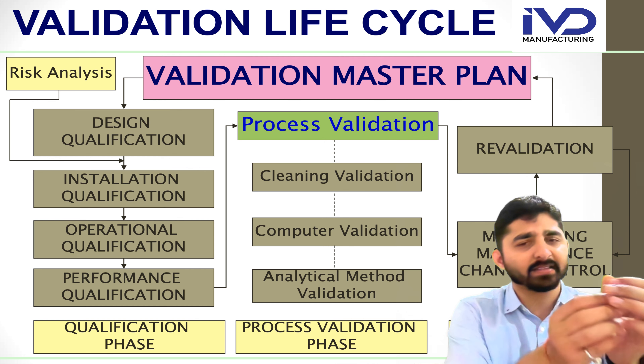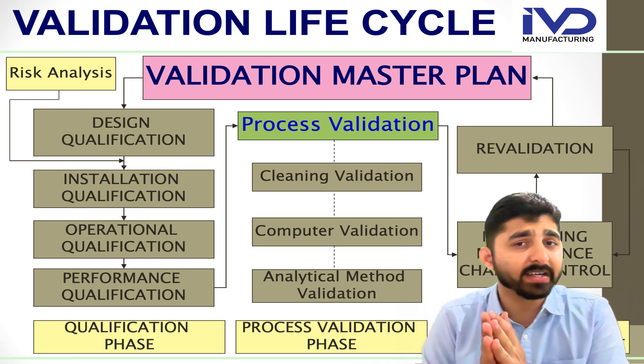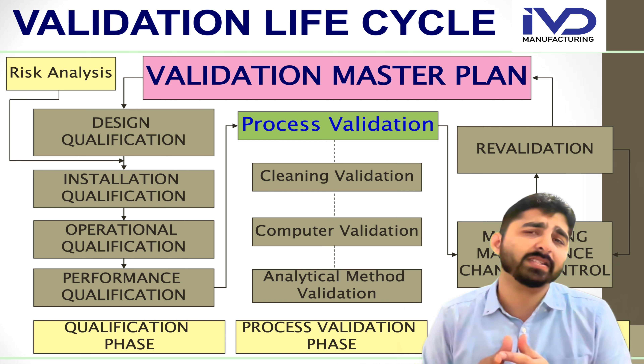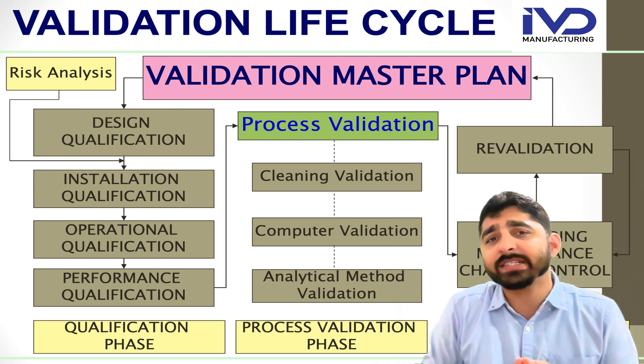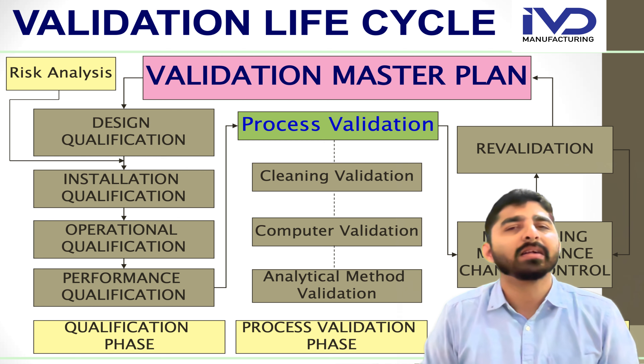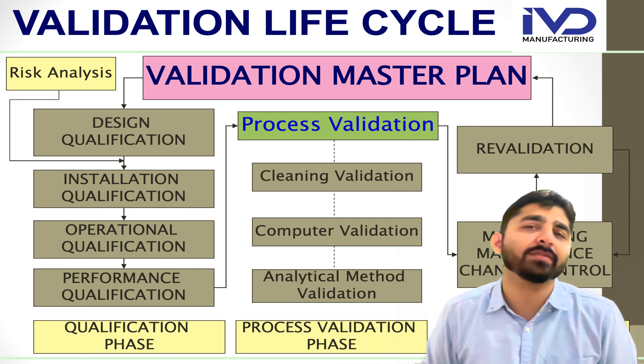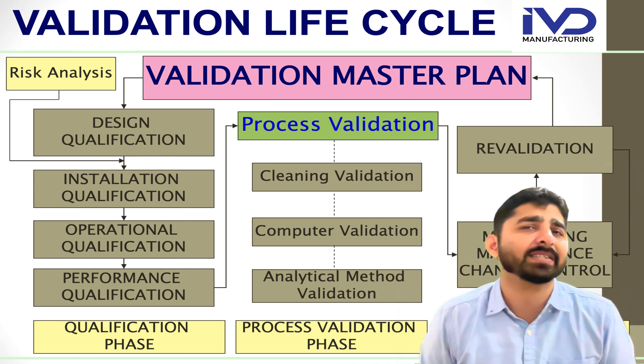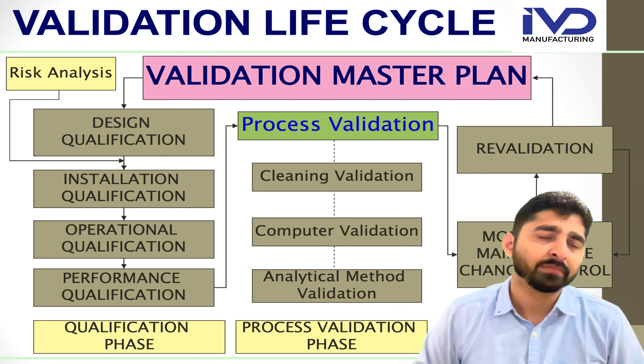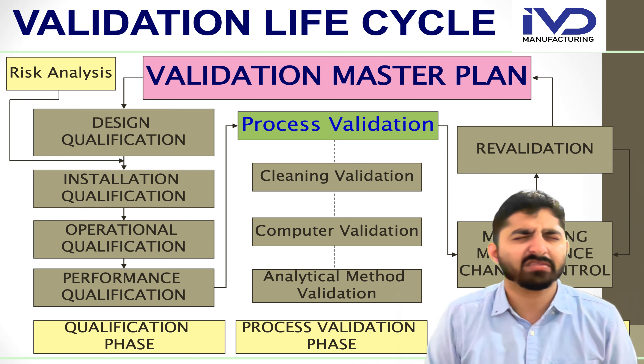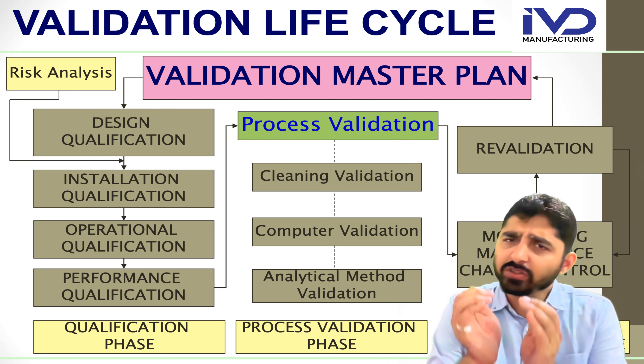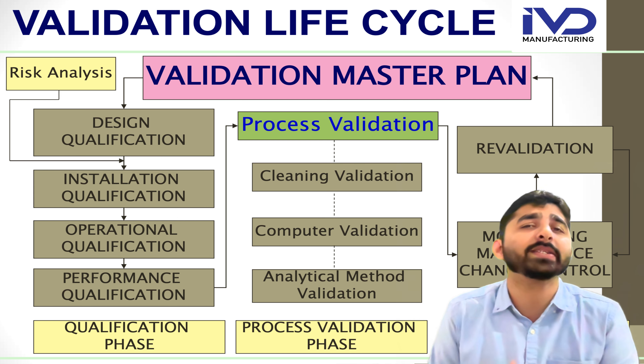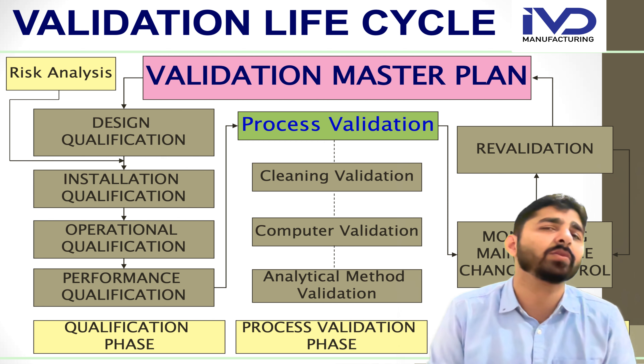Once the qualification phase and process validation phase are finished, I need to set up a frequency for the revalidation cycle based on the criticality of the processes. For example, in manufacturing a medical device such as an IVD — in vitro diagnostic — kit for a rapid test, there are critical processes like conjugation and drying processes. Since those processes directly impact the end result of the product, I need to determine at what duration I am going to conduct revalidation.